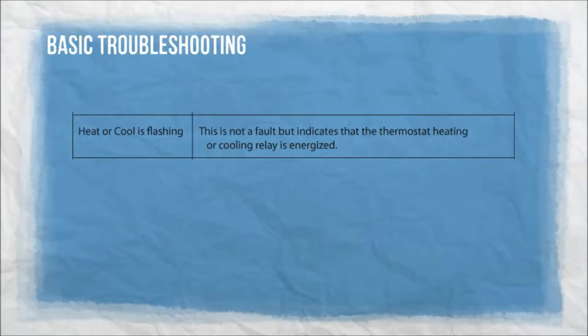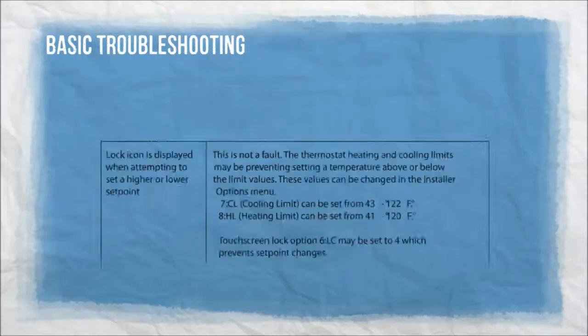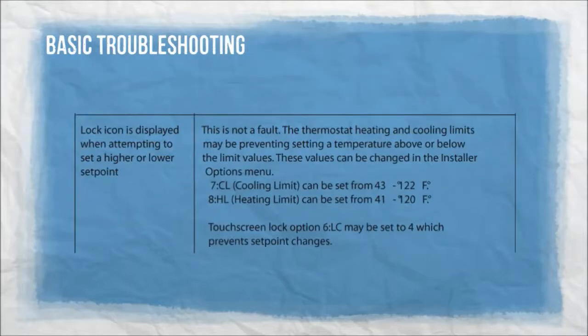Heat or cool is flashing — this is not a fault, but indicates that the thermostat heating or cooling relay is energized. Lock icon is displayed when attempting to set a higher or lower set point — this is not a fault. The thermostat heating and cooling limits may be preventing setting a temperature above or below the limit values. These values can be changed in the installer options menu: 7CL for cooling, 8HL for heating. Touch screen lock option 6LC may be set to 4, which prevents set point changes.